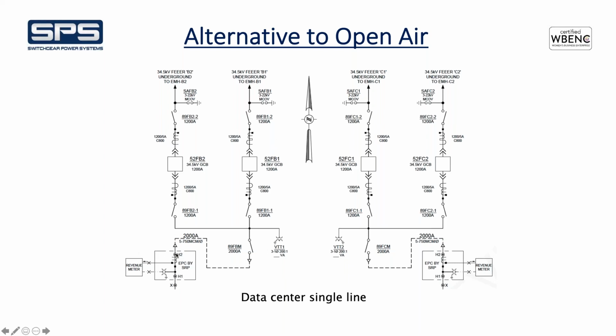So outside of this revenue meter, which is supplied turnkey by the utility, they go underground from the metering, and the rest of what you see in the single line will be incorporated into our switchgear. So main disconnect switch of 2000 amps, and then the disconnect switches on both sides of each circuit breaker. We'll also be supplying the voltage transformers, current transformers, obviously, surge arresters.